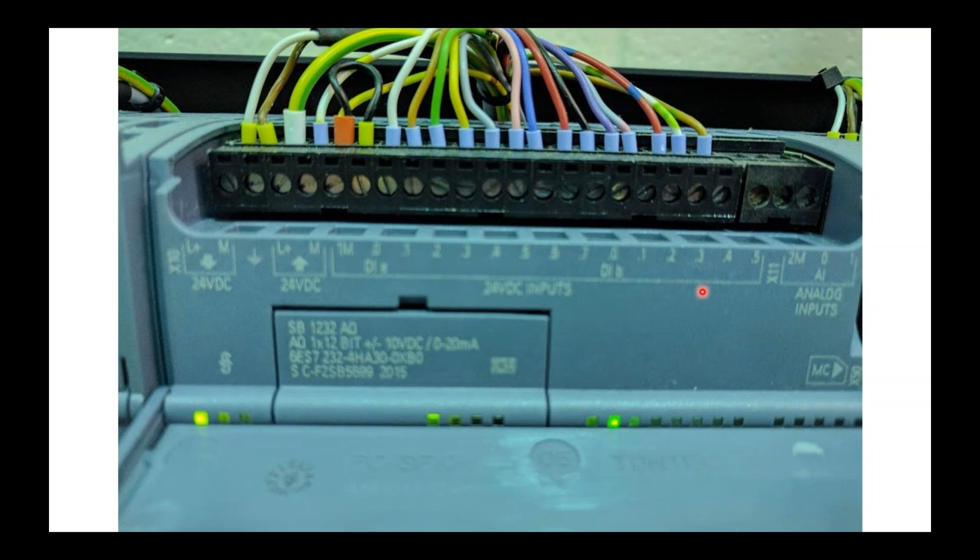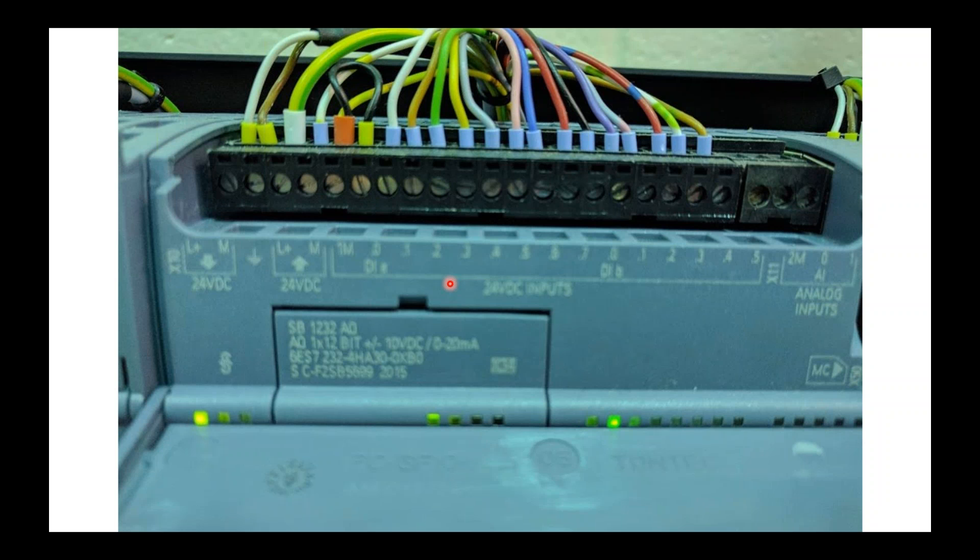In the 300 series, your first set of inputs would usually be a 0 and 1. Your second set of inputs will be a 2 and a 3, while your outputs will be a 4 and a 5 and a 7 and an 8, and never should those two numbers cross. Not necessarily true in the 1200 series. So be aware of that if you're changing from a 300 series controller to a 1200 series controller.